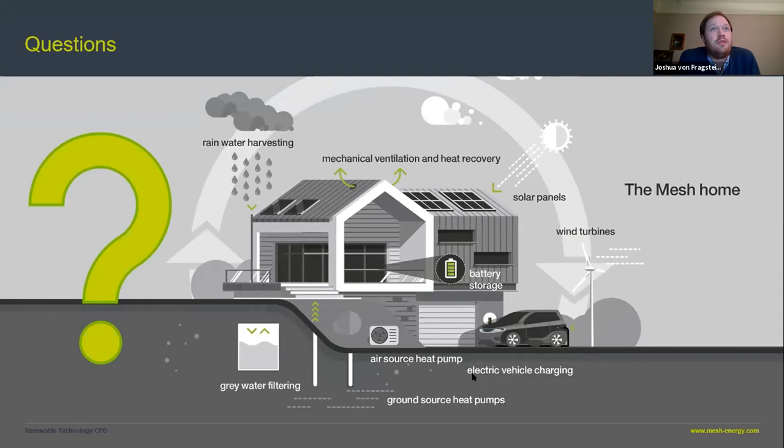They're asking, how much more expensive is a borehole GSHP compared to the horizontal collectors that you've described here? So boreholes are typically about 1.5 times the cost of a horizontal collector system. This is a very rough figure. With a borehole collector installation, one of the main costs is actually getting the borehole drilling rig to site. So with very large commercial installations, you'll nearly always find they're done on boreholes, partly because of the availability of sufficient amounts of land, but also because you've got the drilling rig on site and set up, and it's then relatively quick to drill multiple boreholes. So the answer does depend on the scale of the project. But if I had to give a rough figure, I'd say it's probably about 1.5 times the cost of horizontal.